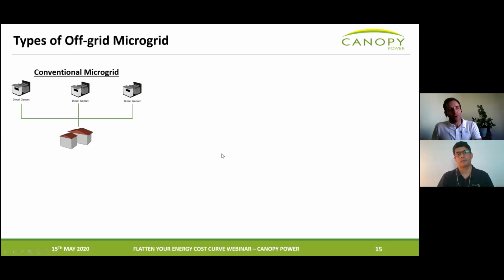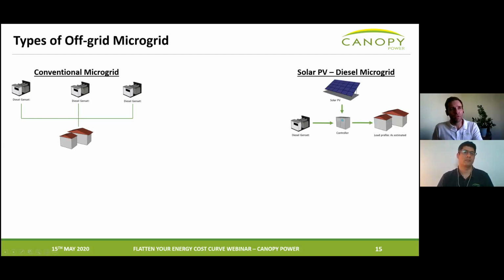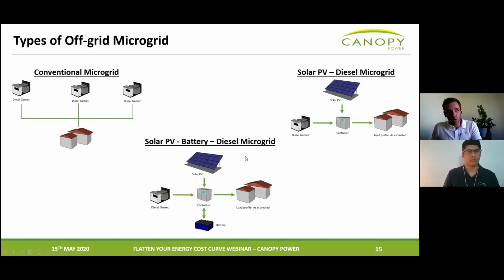A quick review of the types of microgrid. We've got the diesel-only microgrid, very simple. We've got the solar PV diesel microgrid, where we just add solar PV and the controller. The controller makes sure the diesel generator isn't damaged by the solar PV, so it throttles the solar if the diesel genset was ever going to go below a certain threshold. Then we have the full solar PV battery diesel microgrid, where energy storage is integrated. This is really the one that solves most of the problems, and we're focusing on that solution.